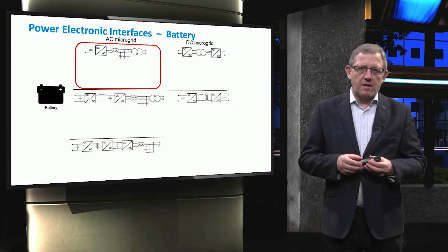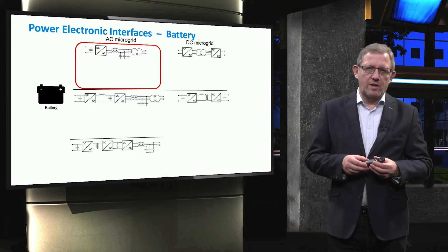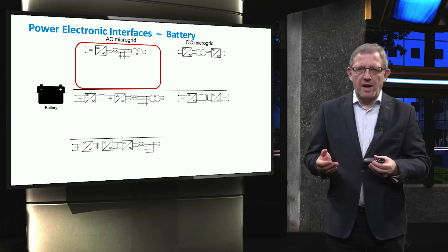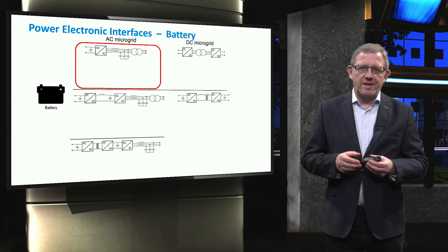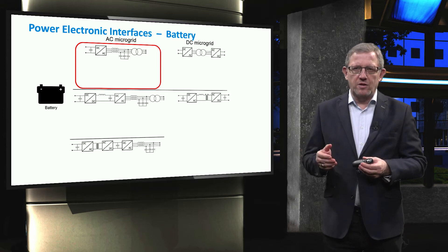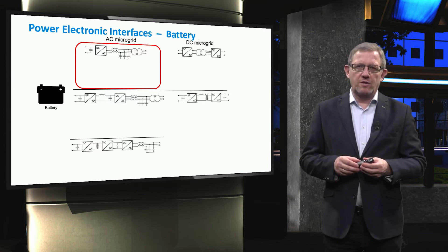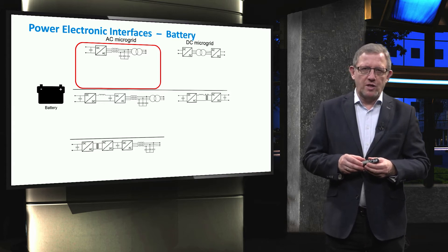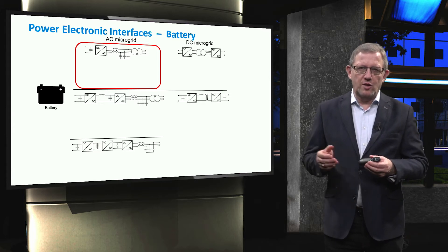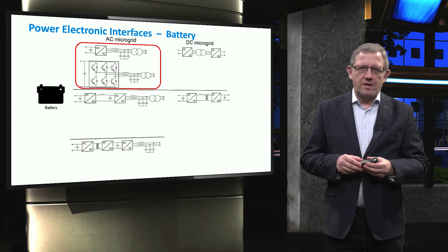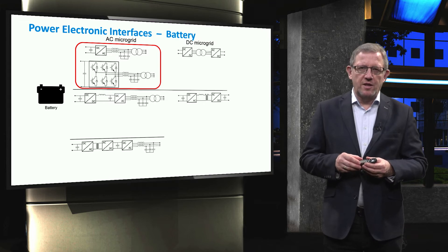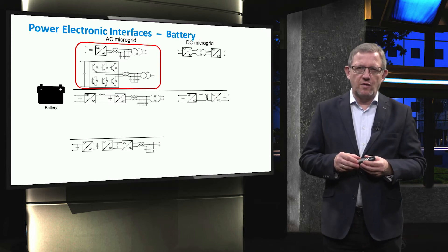Batteries are undoubtedly one of the most important storage technologies for microgrids. To connect a battery, which is inherently DC, to an AC microgrid in the simplest form, a DC to AC converter can be used. A transformer can be used to step up the voltage, for instance from the low to the medium voltage levels. The DC to AC conversion can be achieved through a single stage three-phase six-switch inverter.